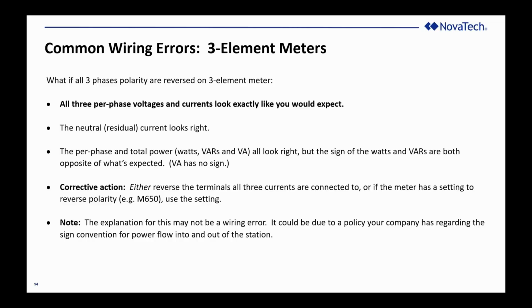So your company policy might be why the three phases are wired in reverse. You want to know that. If it turns out that you need to reverse all three phase currents, some meters have a configuration setting where with the check of a box in the settings in the configuration, you can invert the polarity because some utilities have an opposite convention for the signage of the watts and VARs going into and out of the bus. So if you've got that, like on an M650, you may be able to fix it just by checking that box in the settings.